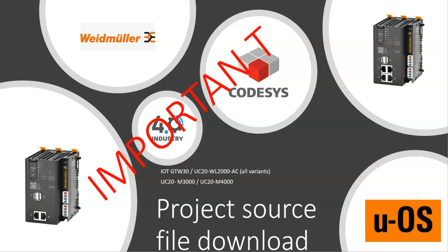If you're a system integrator, you might want to download the project and not allow a third party to upload it and edit your work. So there are some advantages, but obviously you always need to keep a copy of your project. I would suggest you keep 2 or 3 copies that are all synchronized, so you've always got an insured copy to refer back to. But there is a way of downloading a copy of the source code onto the controller as an additional backup. So I would advise you to do that.